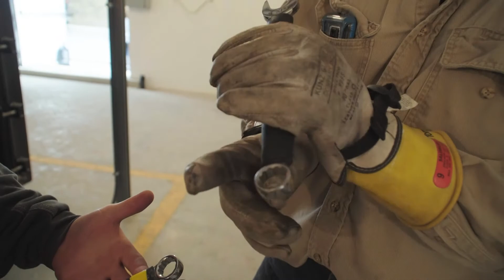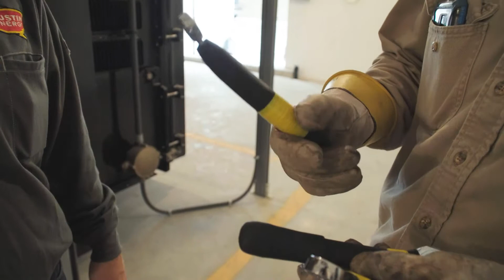So what happened was, this is not insulated. This was connected to the bus. We made contact with the strut with the bottom side. What we have done to fix this is we have now cut our tools and insulated both sides. So now we have one open-ended wrench and one closed-ended wrench. That way we won't have that same mistake of having an uninsulated tool.